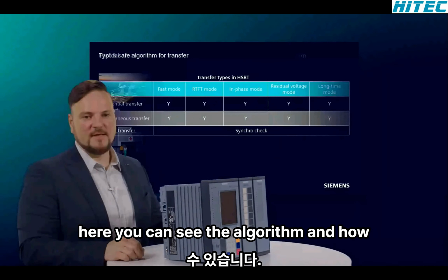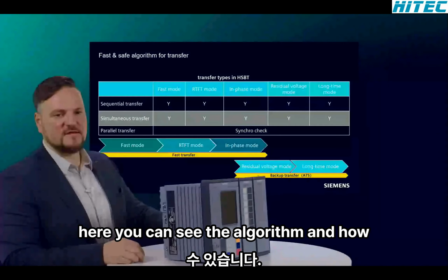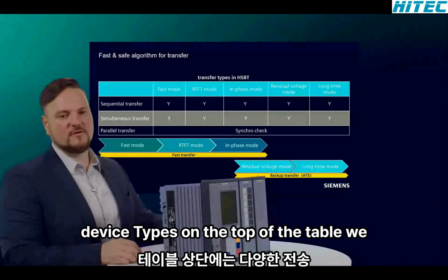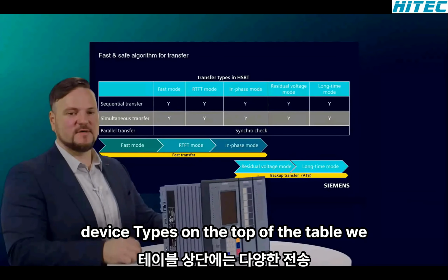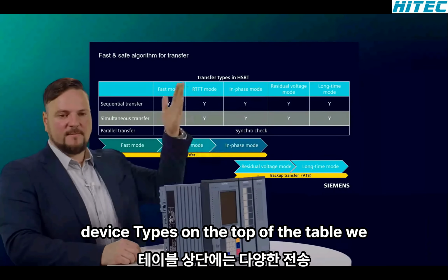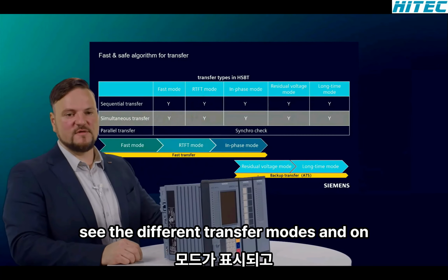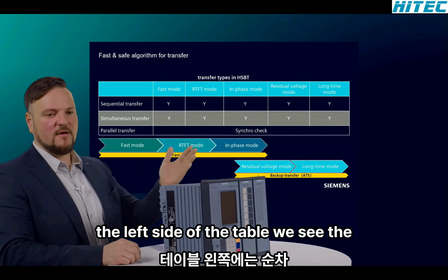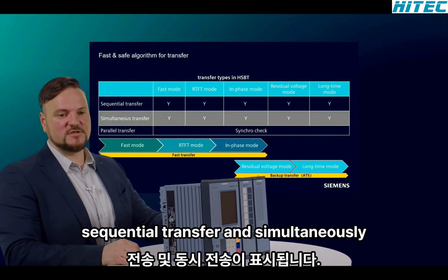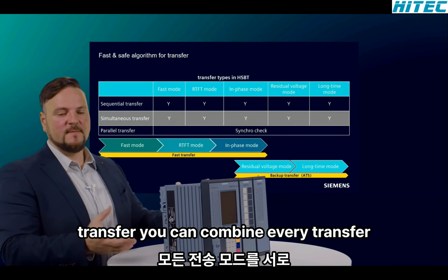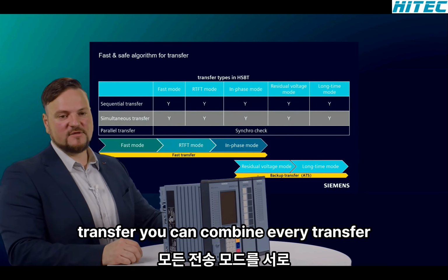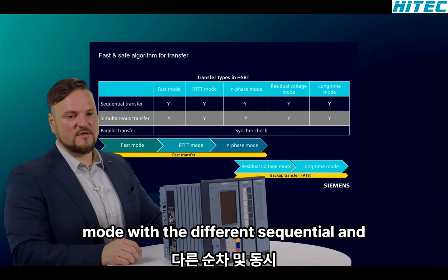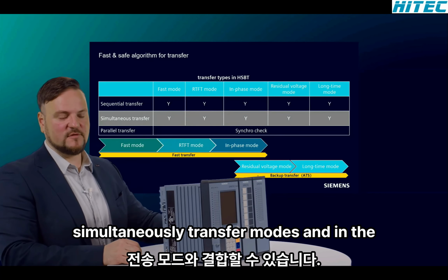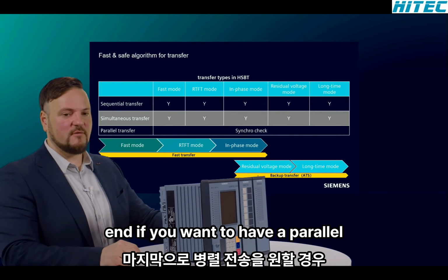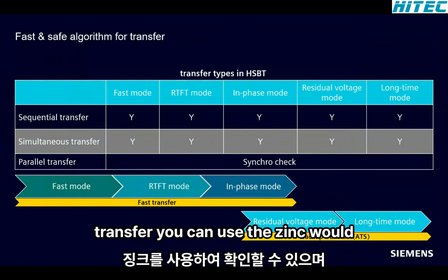Come to the next slide. Here you can see the algorithm and how the algorithm is working in different device types. On the top of the table, we see the different transfer modes. And on the left side of the table, we see the sequential transfer and simultaneous transfer. You can combine every transfer mode with the different sequential and simultaneous transfer modes. And in the end, if you want to have a parallel transfer, you can use the sync check.